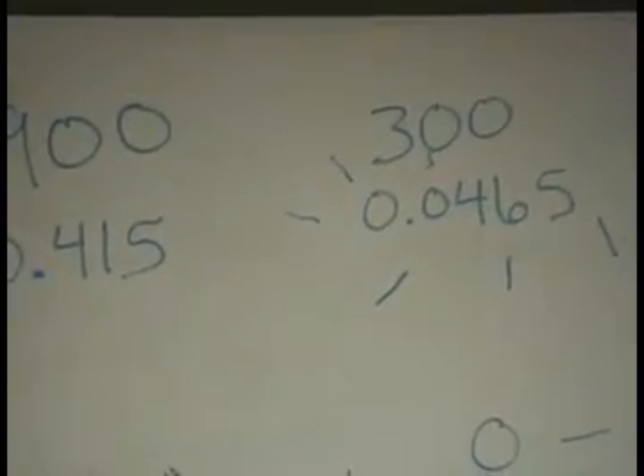And the other thing is by the book, those tubes can't be more than just so long. If it's 1/4 inch, I believe it says 18 inches, and if it's longer than that, they want you to use 3/8. Because if you have too long of a distance, you're trying to send .05 through a little tube 10 feet away, you lose a lot in your lines. So keep those lines as absolutely short as you can. They've got to be absolutely tight, because you can't afford to lose anything.